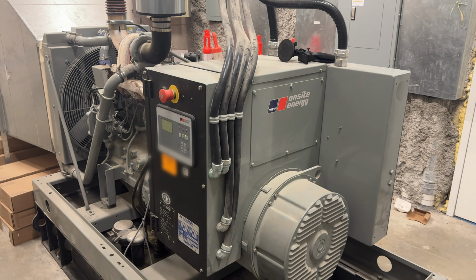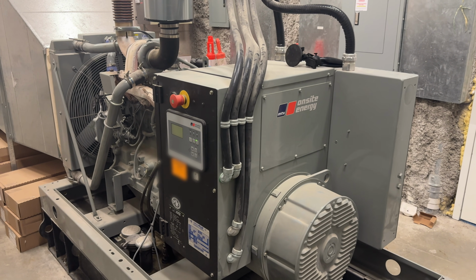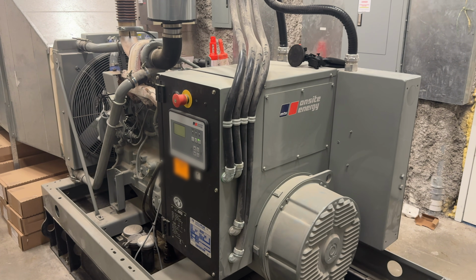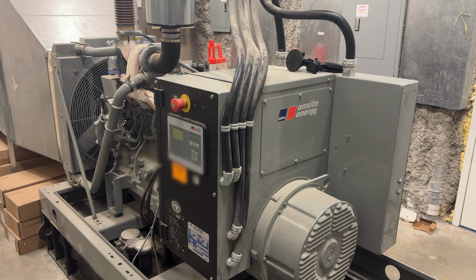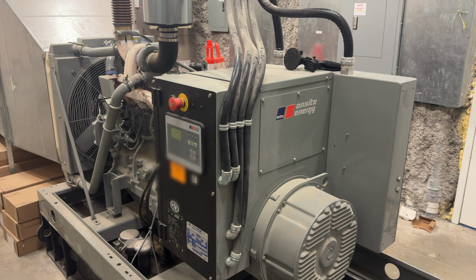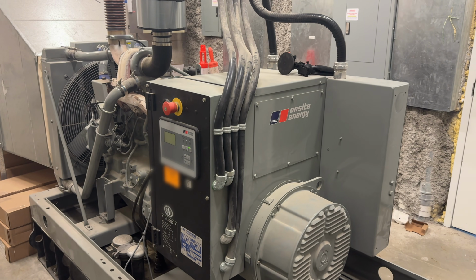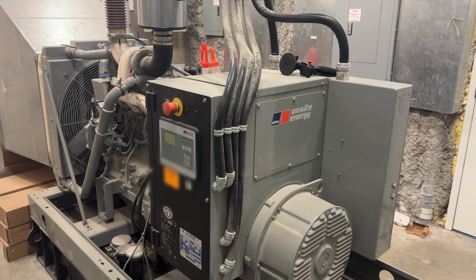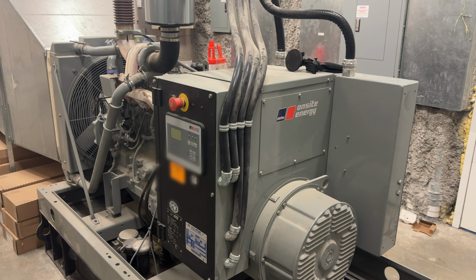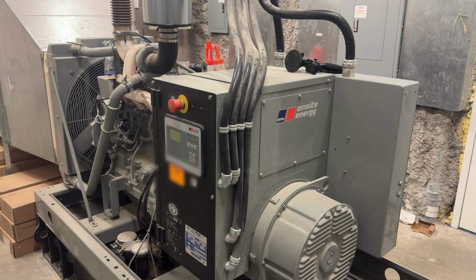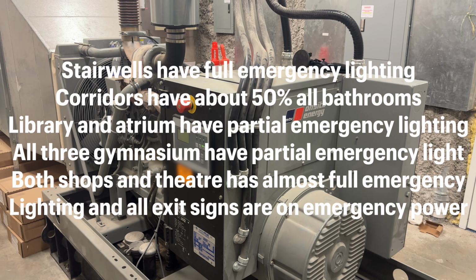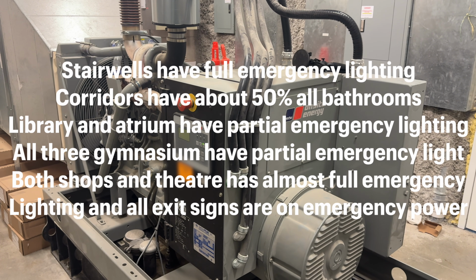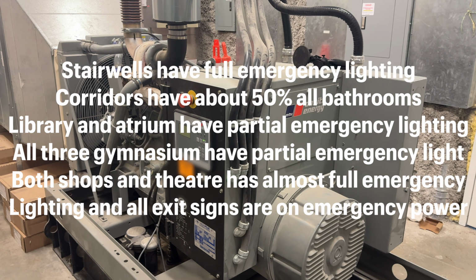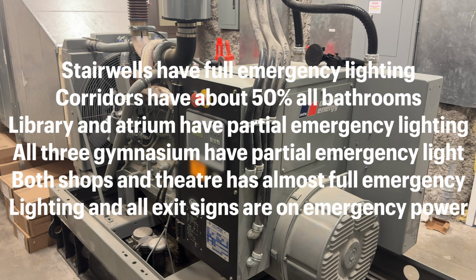This high school needs this emergency generator to power a bunch of different critical loads. Those are the fire alarm system, the huge atrium smoke control system that turns on big fans to suck smoke out, and pressurization fans in stairwells, as well as the fire alarm system itself. And very importantly, this powers all of the emergency lighting. So in your hallways and large occupancy areas, anything with the occupancy over 60, as well as all the lighting in stairwells and bathrooms, those all have to be on emergency power. Therefore, in a power outage, they will keep running.